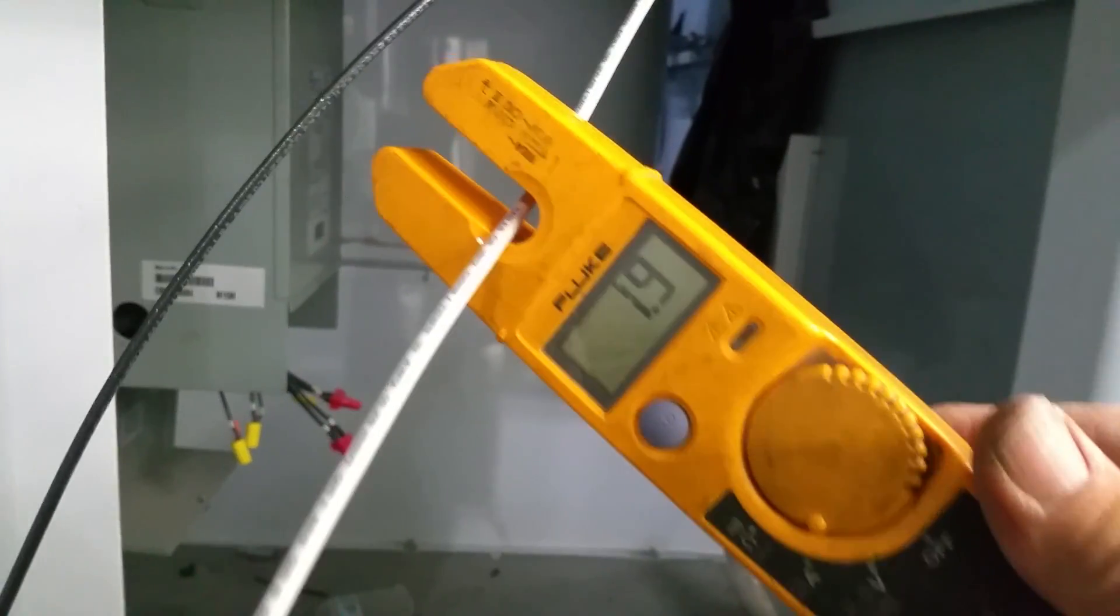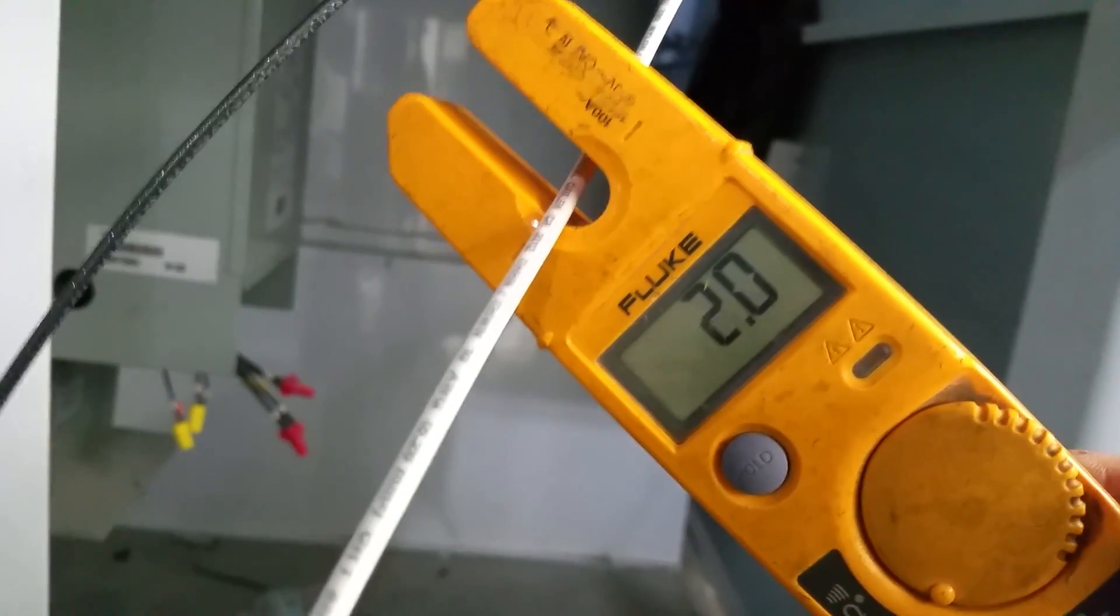Okay, let's hold it up here for a second. What do you think is going to be on this neutral? Is it going to be 40? No, it's not. All the neutral is responsible for is to carry the imbalance of the load. Here you're seeing two amps of neutral load.